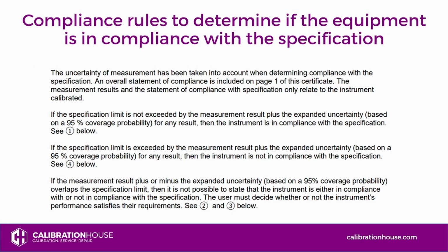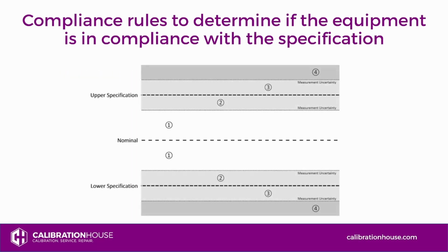A UKAS certificate also has a statement showing which compliance rules have been followed to determine if the equipment is in compliance with the specification. How has compliance been determined? This is better represented here with a graph. So you can see that your nominal value falls in the center. You've got your two specifications, the two ranges, upper and lower, and then you've got your measurement uncertainty either side of that. And this is explaining how the compliance rules are followed to determine if the equipment is in compliance with the specification.